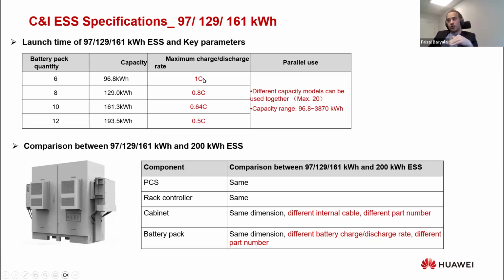Depending on the capacity, the ratio between charging, discharging, and storage capacity can vary. For example, for 96 kilowatt hour, we have a maximum 1C value, which is the highest rate for charge and discharge. This C value decreases as we increase the capacity, going from 96 to 193 kilowatt hour.